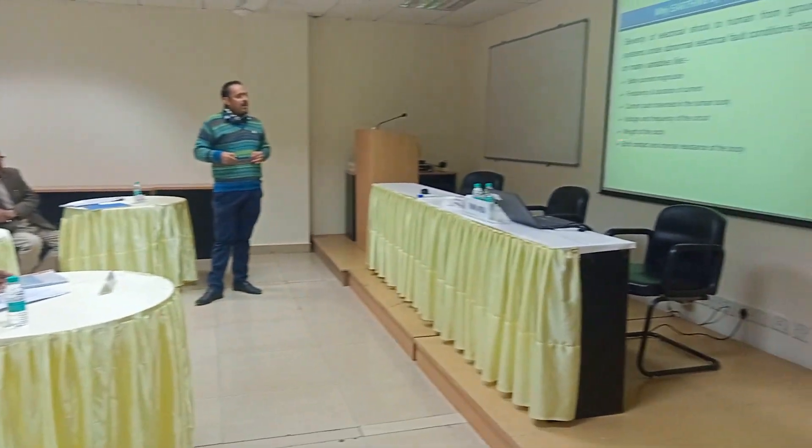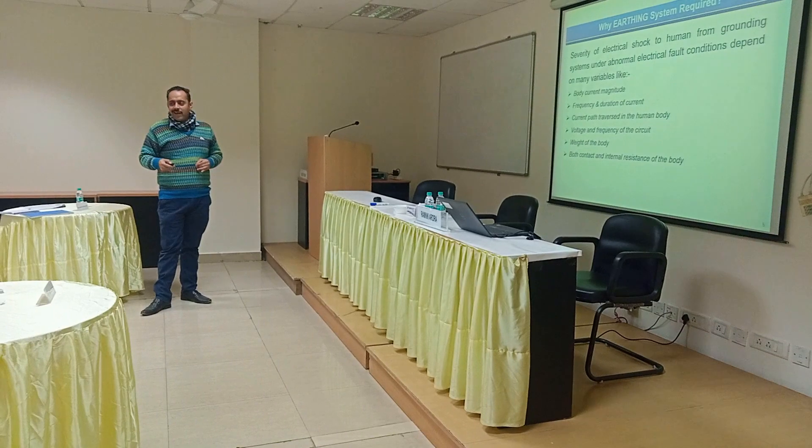Why is a grounding system required? The severity of an electrical shock to a human from a grounding system under abnormal fault conditions depends on many variables: body current magnitude, frequency and duration of current, current path through the human body, voltage and frequency of the circuit, and weight of the body — both contact and internal resistance. In IEEE standard we have a 70 kg weight and also a 50 kg weight, because you don't know who will be in the substation when you are doing your design.